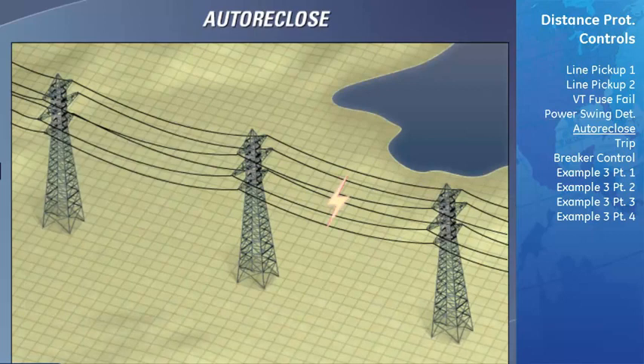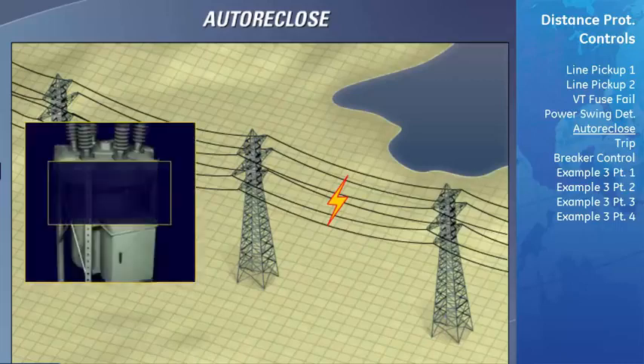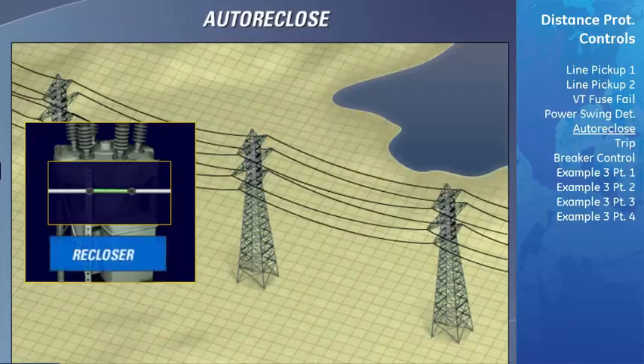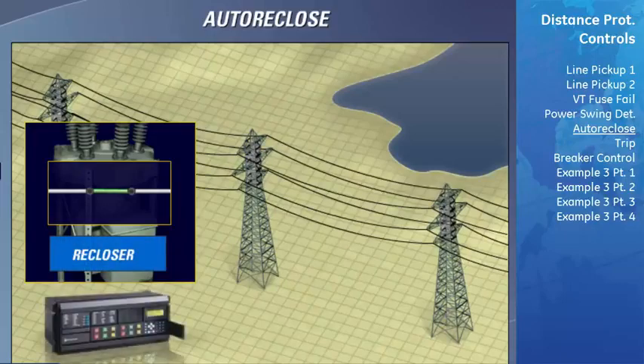As mentioned before, many faults that occur on transmission lines are transient in nature. That means that the fault is temporary and no repairs need to be made. Simply tripping the breaker and then after a time period reclosing the breaker is sufficient to clear the fault and bring the transmission line back into service. Historically, a separate device known as a recloser was used to perform the delay and closing of the breaker. Modern multifunctioned relays such as the D60 have this feature as a built-in element that can be used. It is known as the auto recloser.